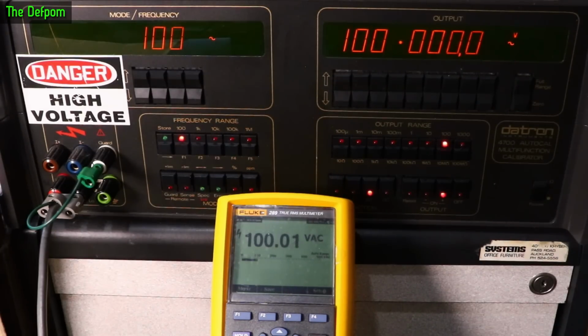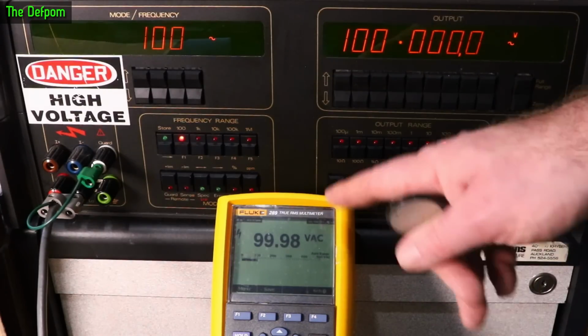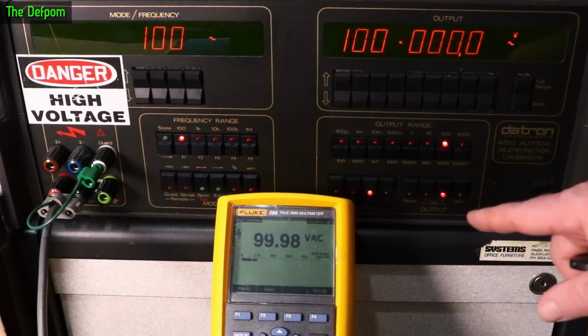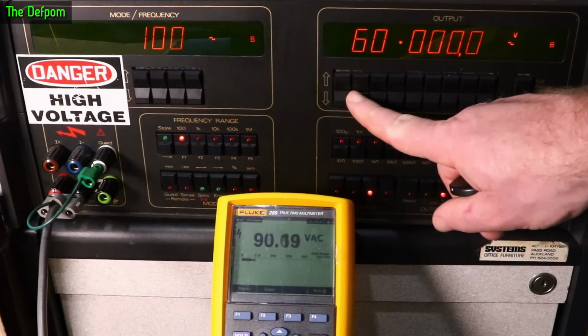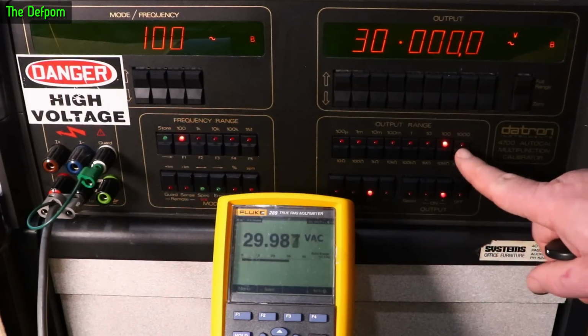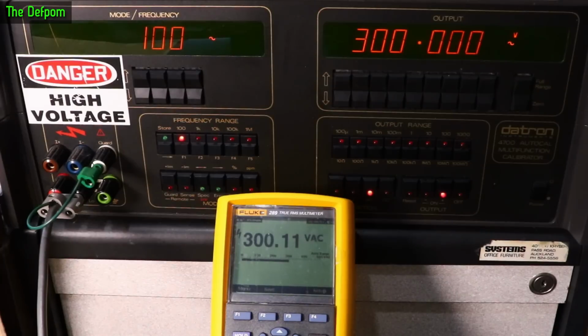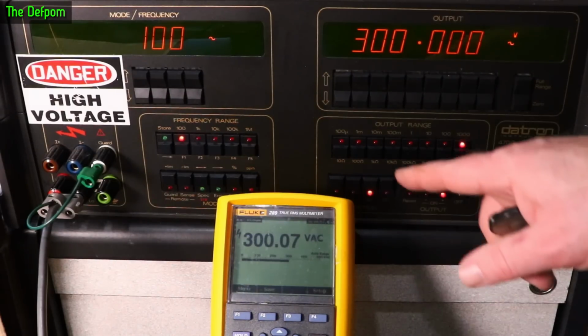Give some settling time. Yes, 1 to 2 counts down at 100 volts. Okay, let's do the same 300 volt test. It's got a lot of settling time on there. It's obviously using averaging of some kind, even though it does have averaging as an option, I think, but that was turned off. So it's obviously got some other averaging built into it. Smooth the readings out a little bit. So about 7 counts high, not too bad.